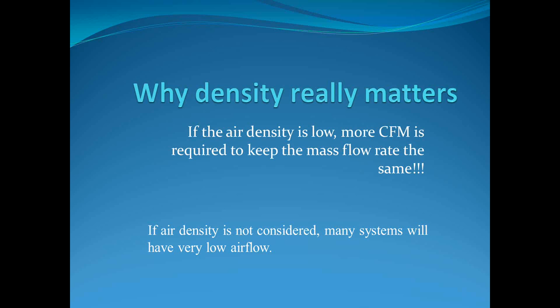Why density really matters: if density is low, air has less mass and less ability to carry heat energy, so you'll need more CFM to keep the mass flow rate the same. Interestingly, if air density is not considered, many systems will show low airflow — which connects directly to that statistic that 70% of systems have low airflow. Paying attention to air density can help keep systems out of that problem category.